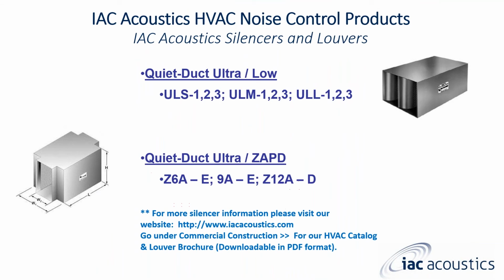We have our quiet duct ultra low silencers. These actually enhance the 31.5 octave band. And then we have our quiet duct ultra zero added pressure drop with the wings on the outside. These are the baffles on the outside. There are no middle inner baffles. These are kind of stuck right now with an open width of 6, 9, or 12 inches. You can take this at any height that you want, but for right now, we are looking at adding a larger line of this as well.